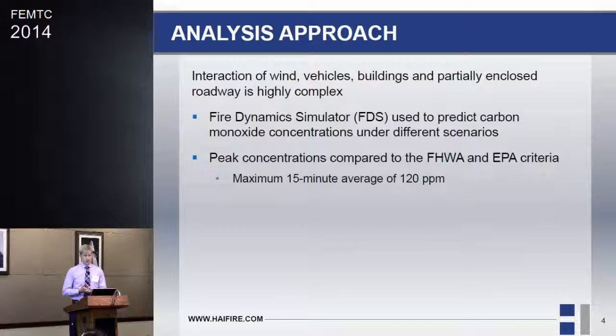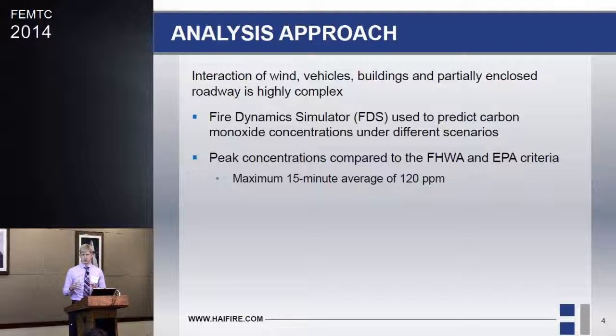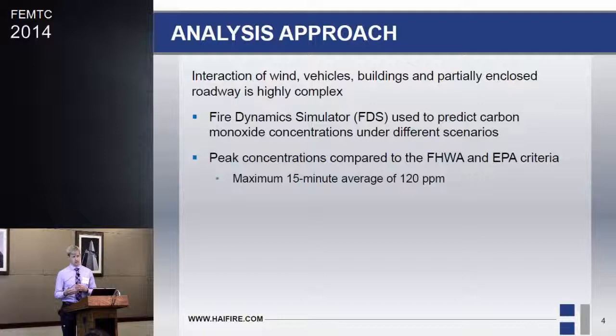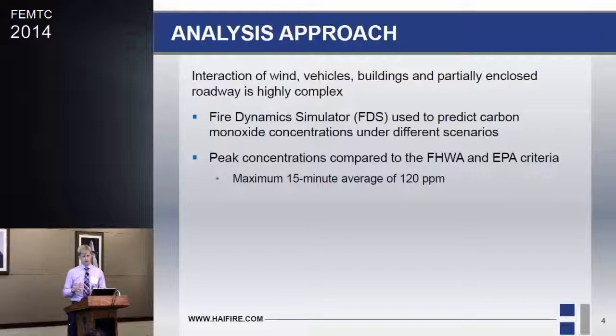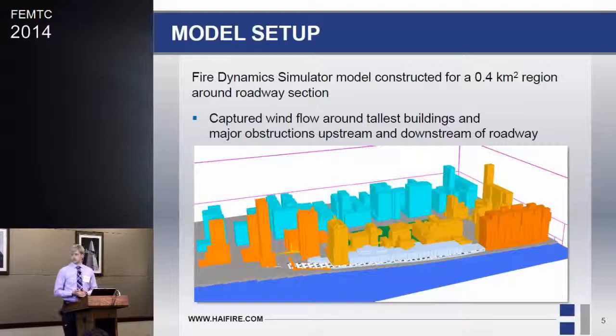Due to the high complexity of the interaction — several hundred cars each putting out carbon monoxide, wind from different directions, and the large urban area with buildings in all directions — we used FDS to predict carbon monoxide buildup, identify areas of concentration, and compare to EPA criteria over a 15-minute average. The obvious solution would be to install an exhaust system to blow through the enclosed roadway and clear out the CO, but they wanted to know whether they actually needed that, and if so what flow rate would be required.